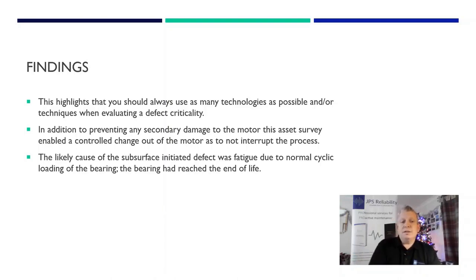So the likely cause of this was a subsurface initiated defect due to normal cyclic load in the bearing. It had reached its end of life in this application, but it was due to the drive.